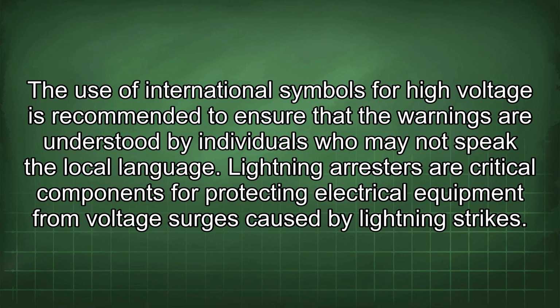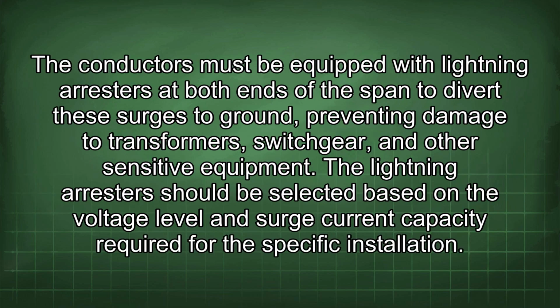The use of international symbols for high voltage is recommended to ensure that the warnings are understood by individuals who may not speak the local language. Lightning arresters are critical components for protecting electrical equipment from voltage surges caused by lightning strikes. The conductors must be equipped with lightning arresters at both ends of the span to divert these surges to ground, preventing damage to transformers, switchgear, and other sensitive equipment.